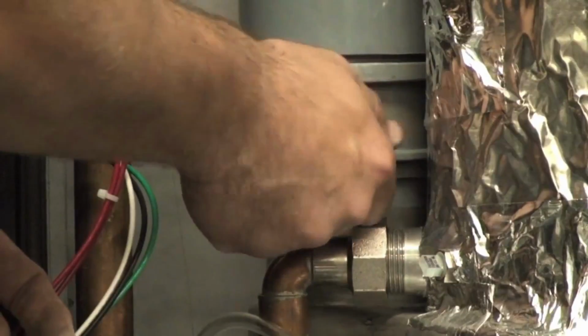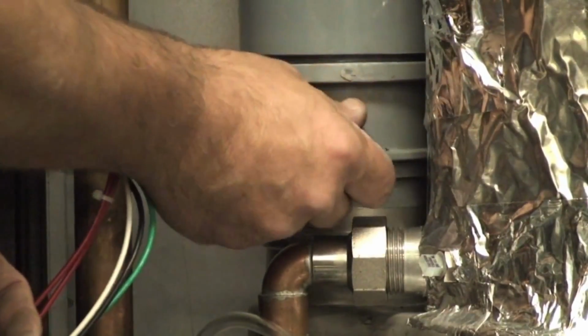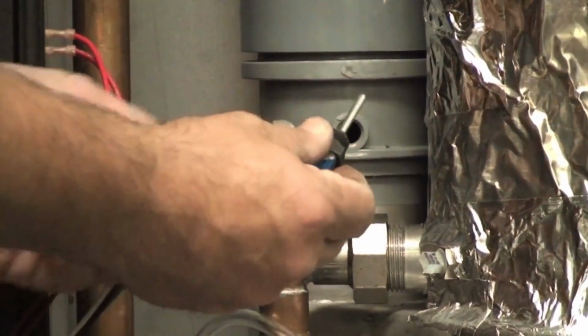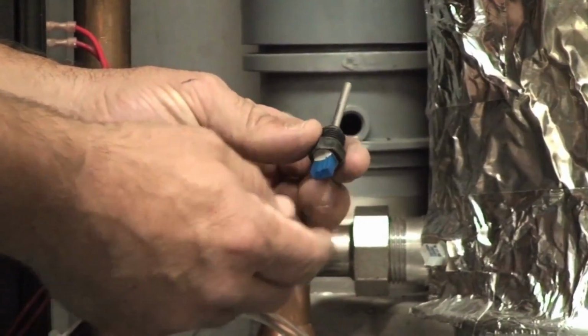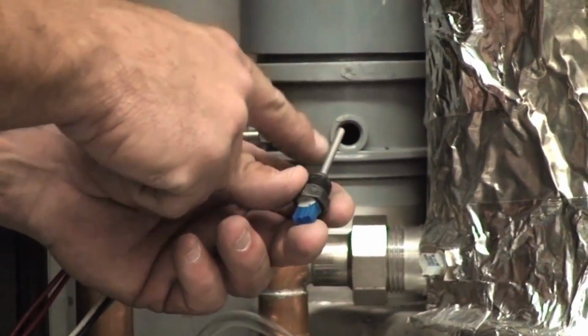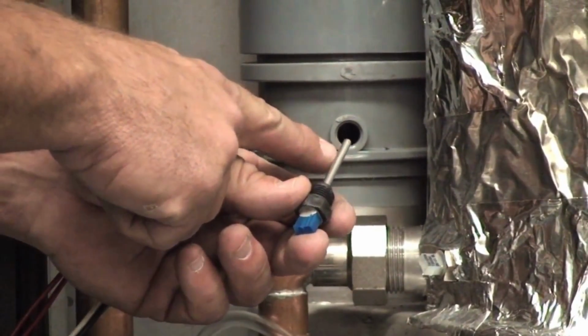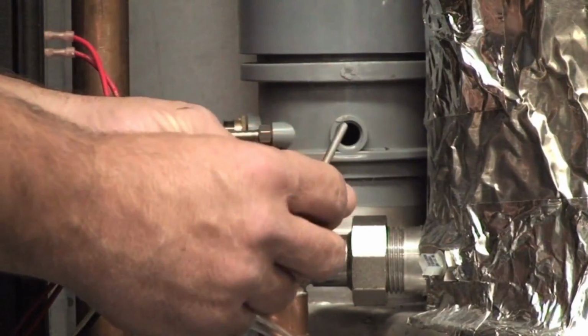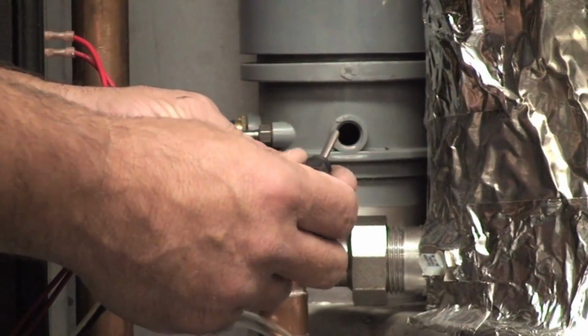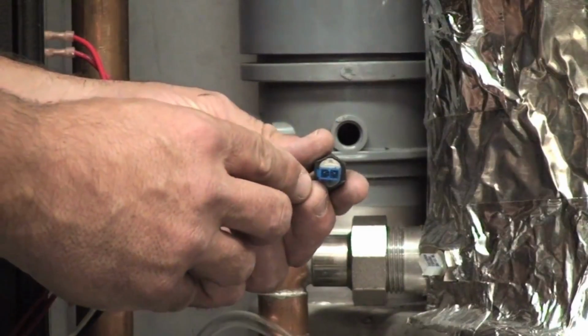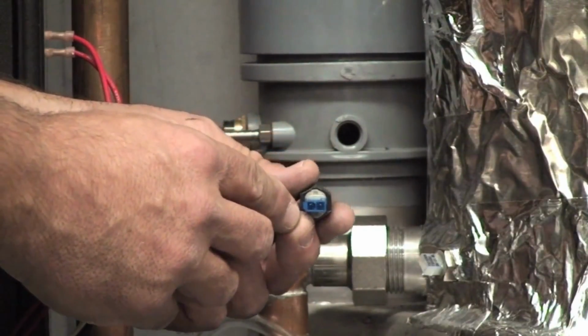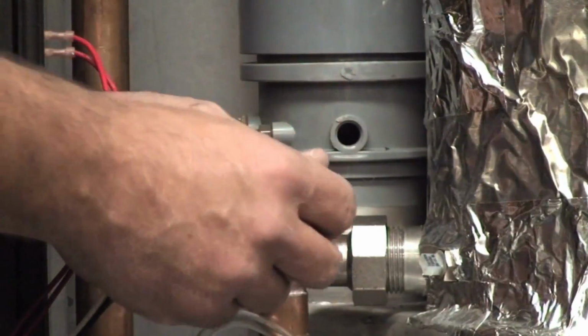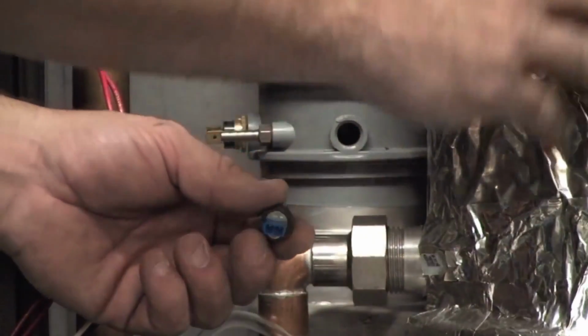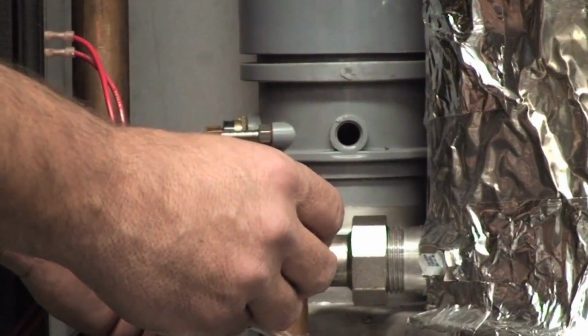The flue sensor. You just unthread it, get it out. It's a standard taper thread, and the sensing element, the NTC element or the sensor, is located at the end. It's all stainless steel with a plastic enclosure, and it's a simple 2-pin Molex connection that measures the temperature inside the flue and measures the absorption rate inside the heat exchanger.